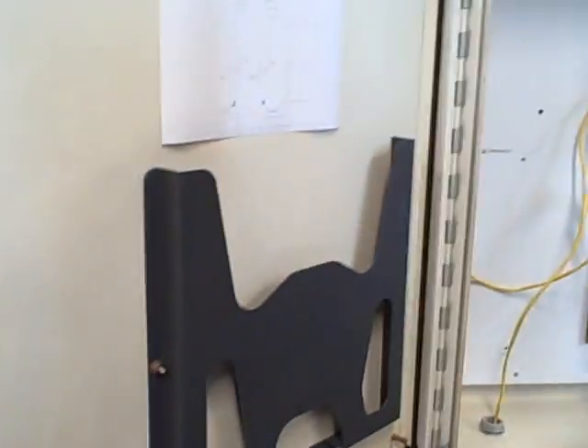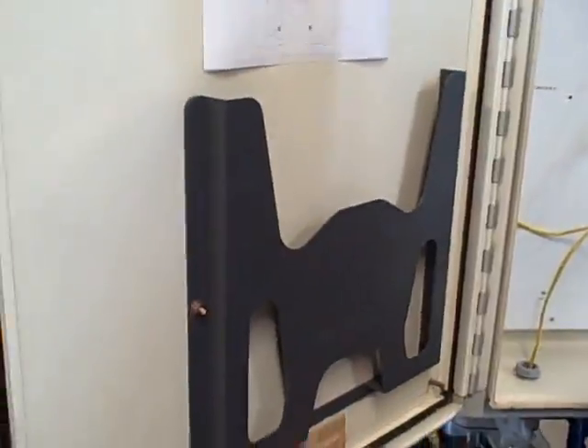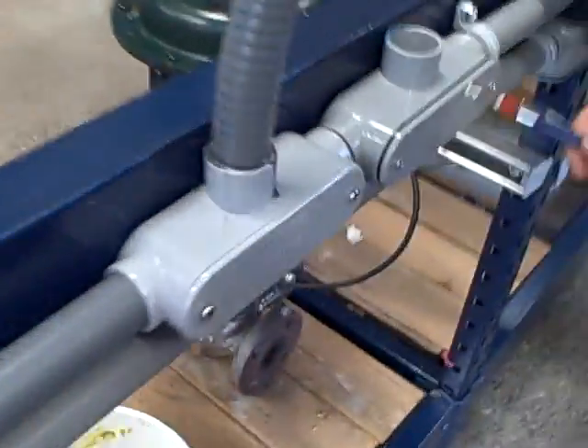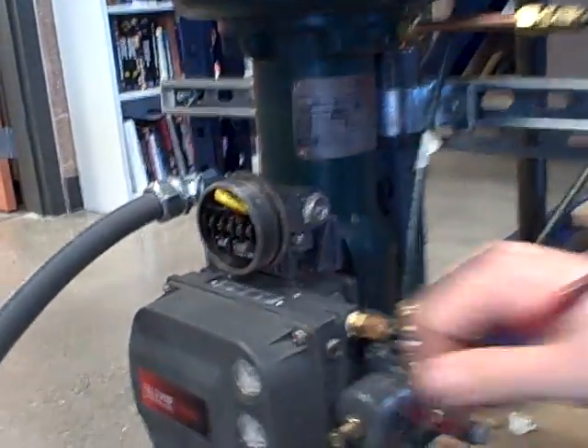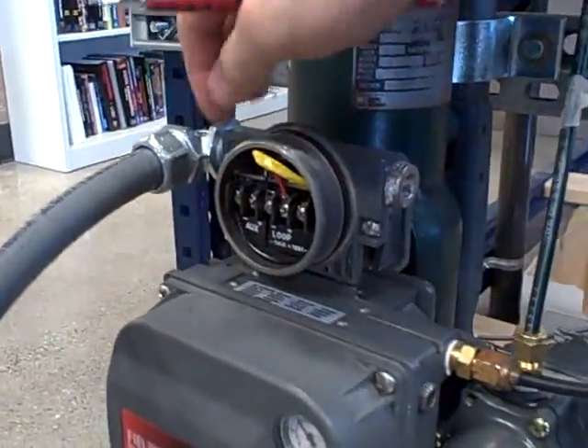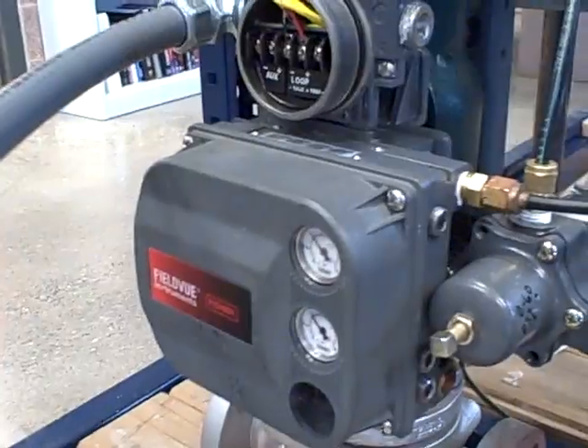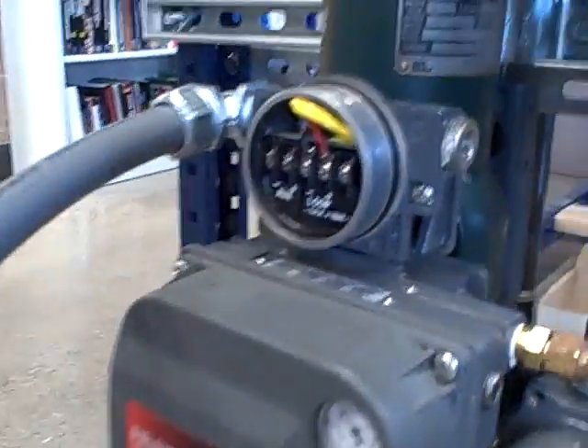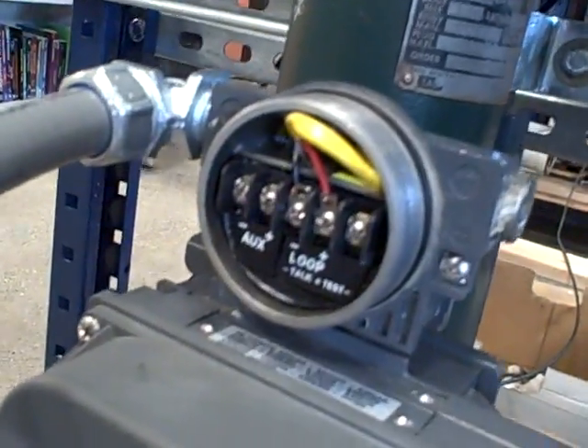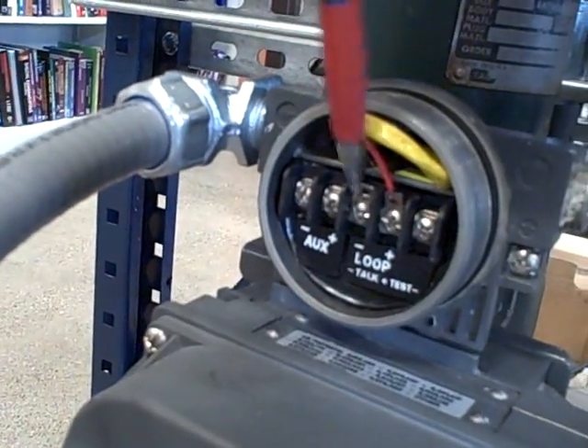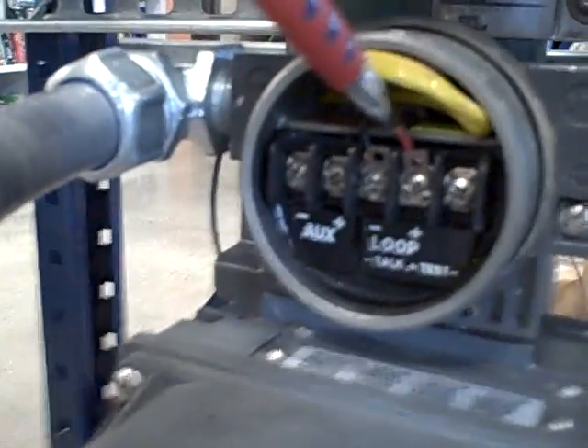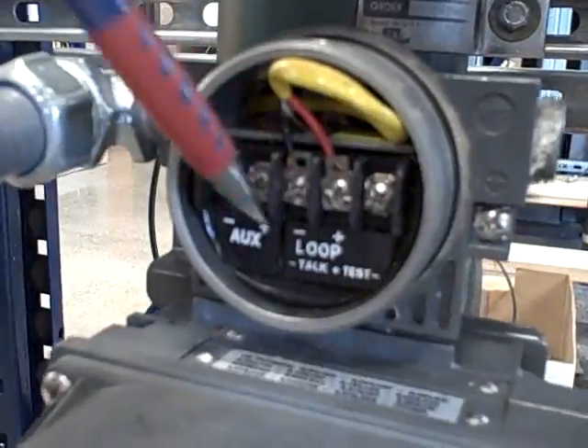All right, and so Ken, let's trace it on from there. We've identified the cable. Where does it go from there? Okay, so it runs down through here and through this conduit. Right. That runs down and to our positioner right down here, through this conduit right here. And that's a DVC-6000 positioner. And this is a DVC-6000 positioner, which is connected to our valve, as you can see here. Right. And we got the black going to our negative and our red going to our positive. Which is correct.